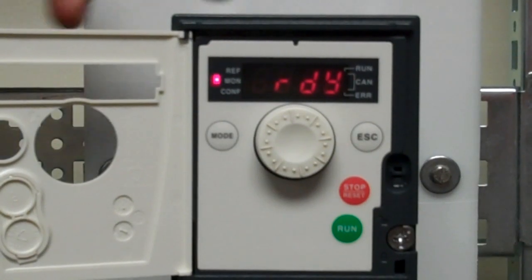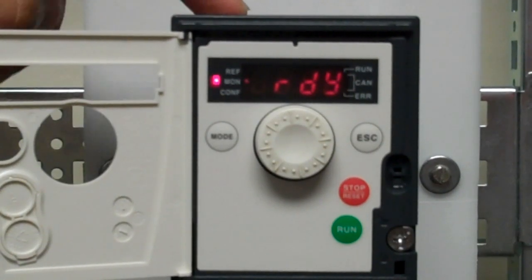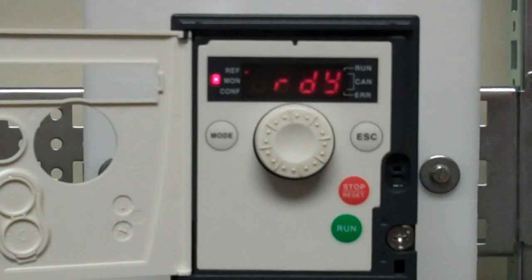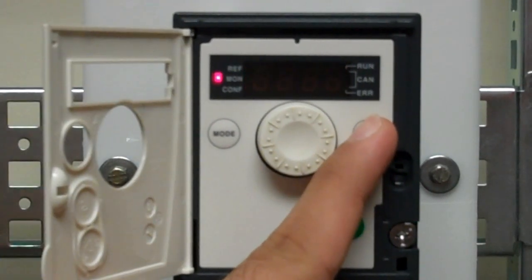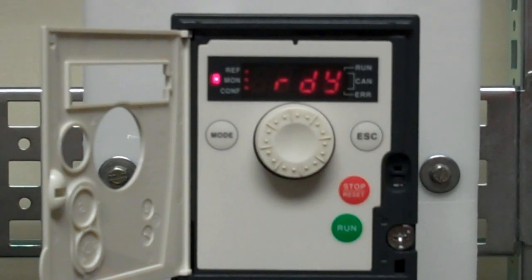Right now your drive is in local control. To change the program to accept commands from your terminals, you'll have to go into programming mode first. To do that, press the escape key and hold it for about two seconds. Your LEDs will change from flashing one at a time to flashing at the same time.